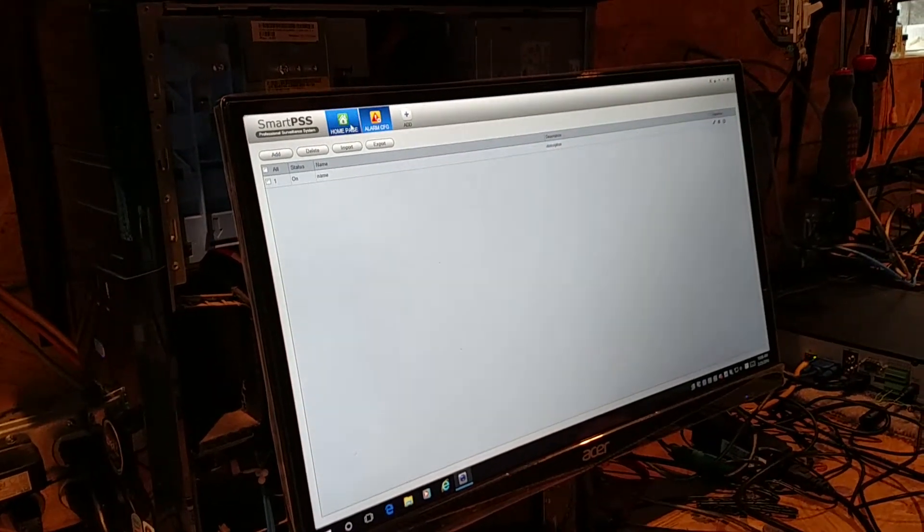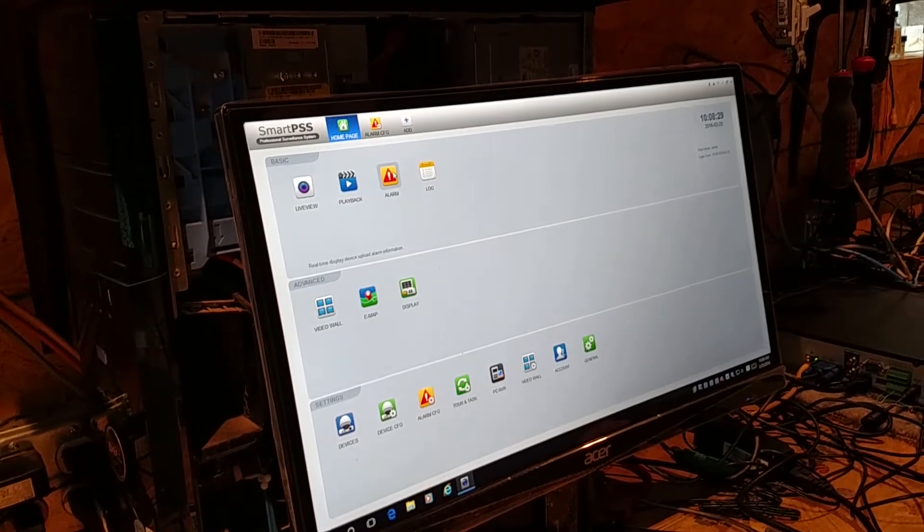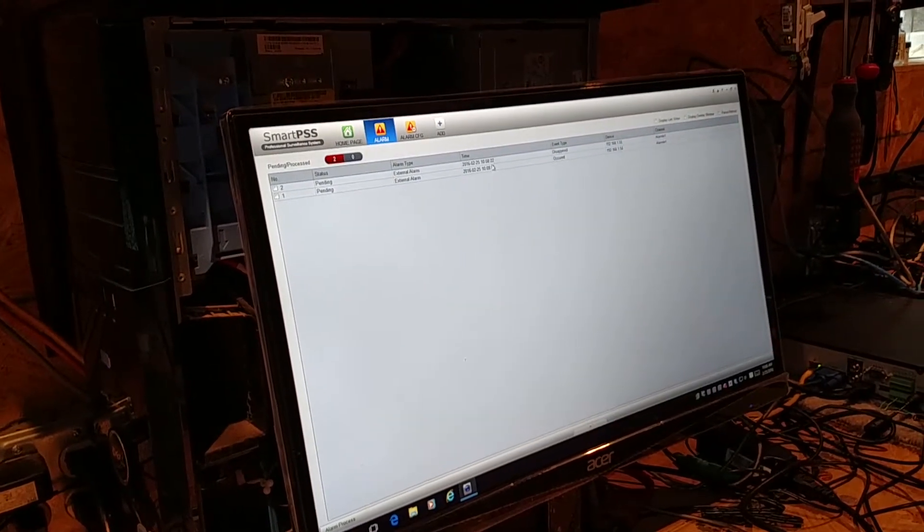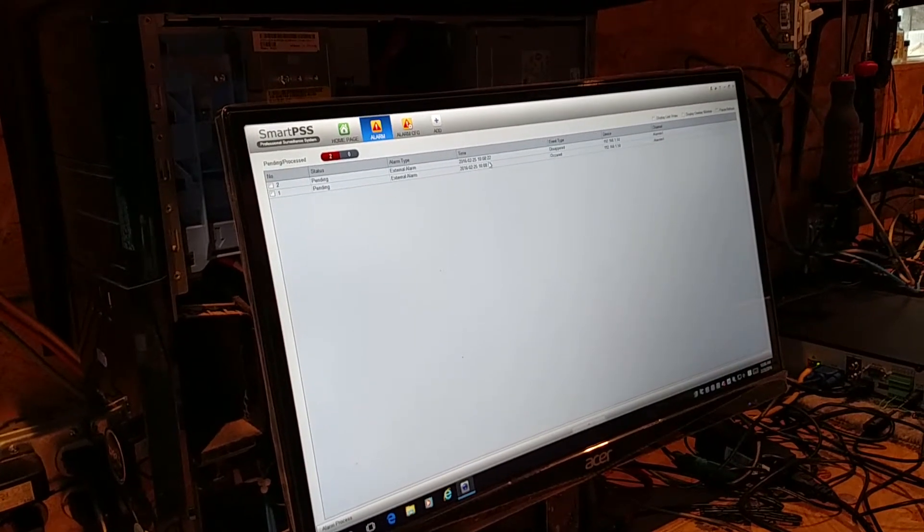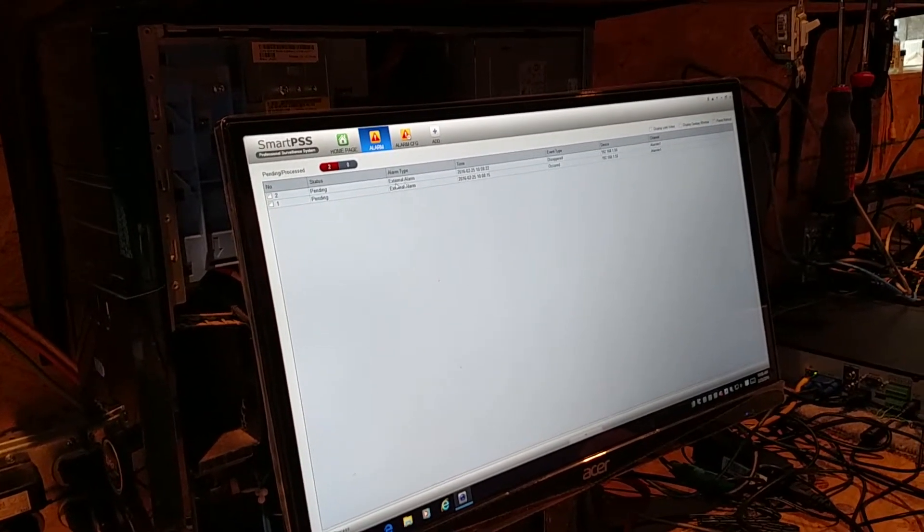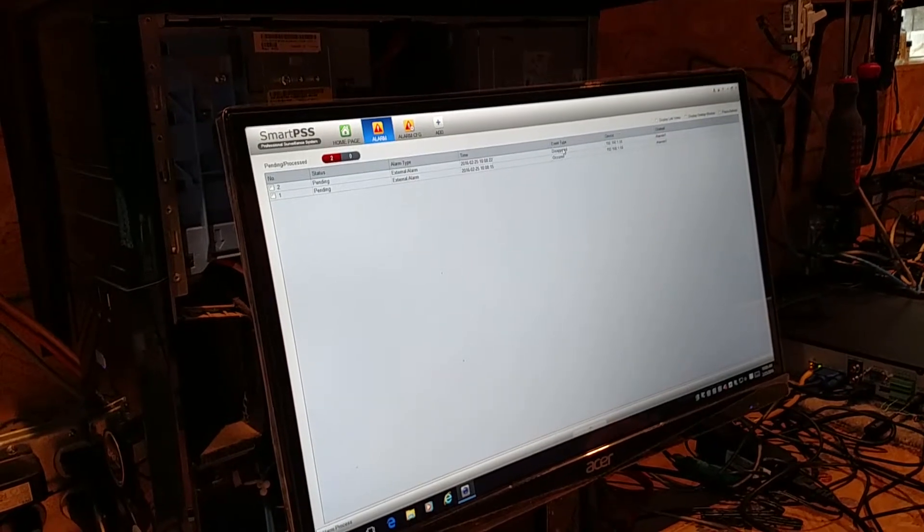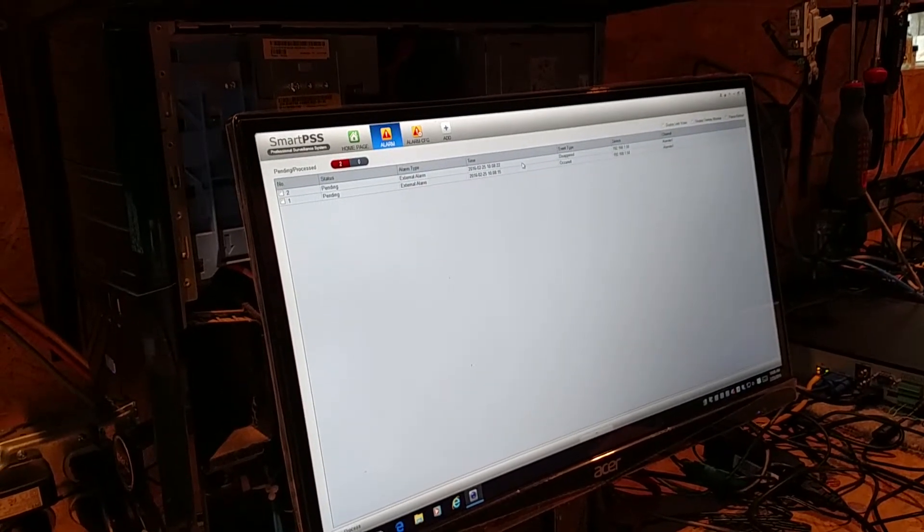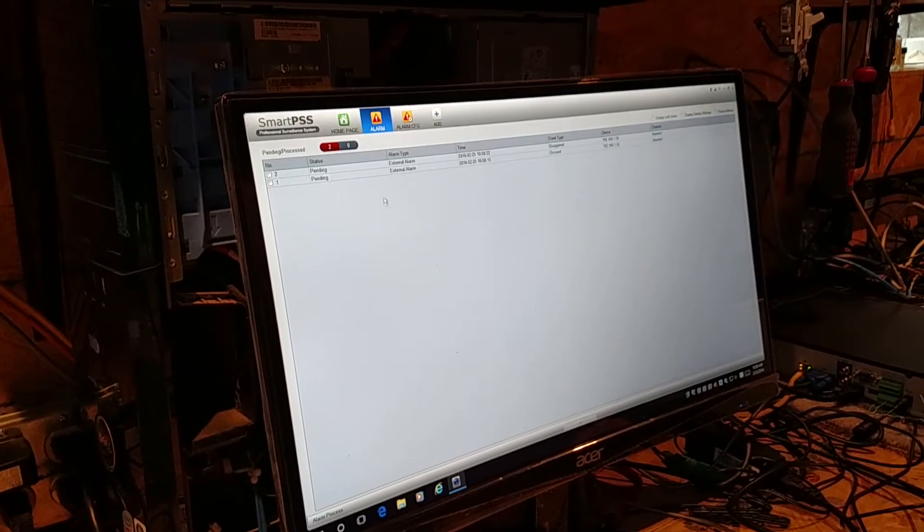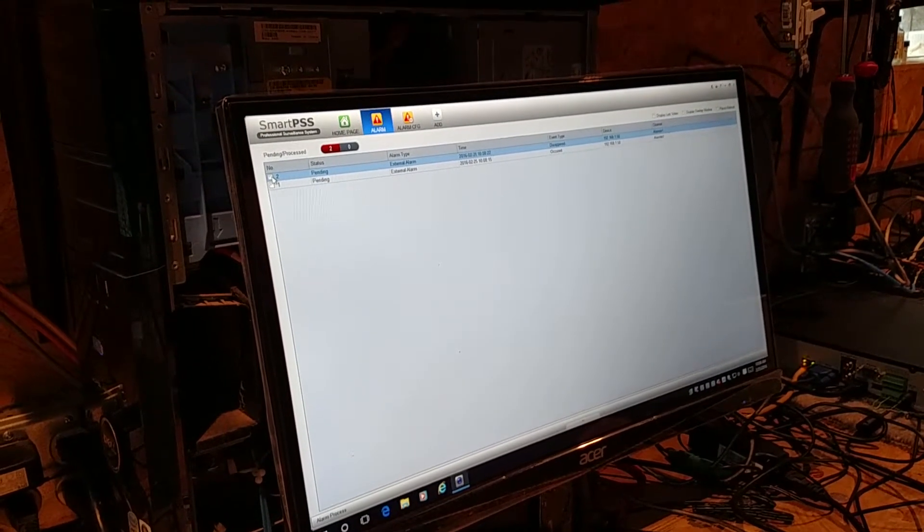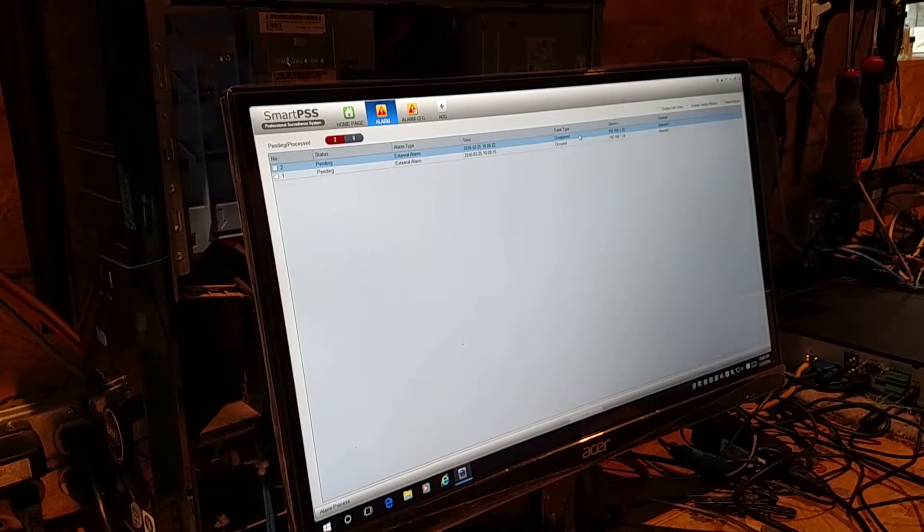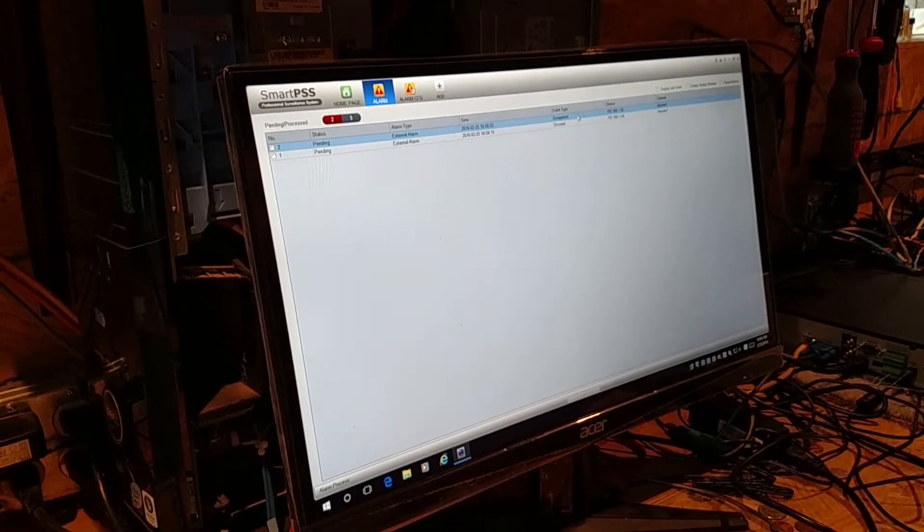So I'm going to close that. I'm going to go to my alarm page. There's two issues here. First issue is the fact that the alarm occurred is valuable information. The fact that it disappeared is irrelevant. So if there's a way that you can create a setting to disable showing up or to filter so we never see the alarm disappear, because that does not matter to the customer.